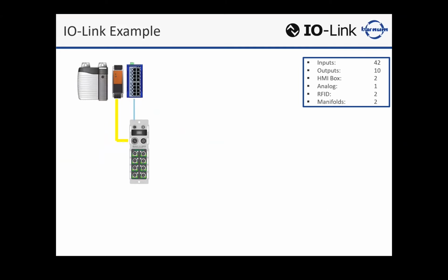We are going to use what you see in this picture called a master block. What a master block does is communicate directly on your upper level protocol, your Ethernet IP, your Profinet. So we do pay for a chipset there that communicates directly back to the PLC, has an IP address, but you'll see on this particular model, there's 8 ports. Those ports are IO link ports. So to those ports, I can connect IO hubs, as we discussed, either IP20 or IP67, discrete or analog IO hubs.